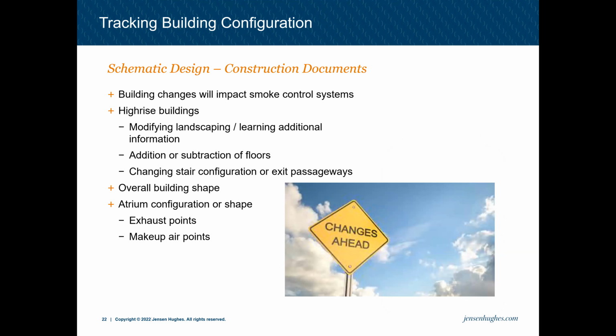So throughout design of a project, we always need to be tracking the building configuration. Building changes can impact smoke control systems. So for instance, for high-rise buildings, if you're modifying the landscape or learning additional information, that we've seen before can change high-rise classification. And we've seen some projects where they start to do sloping and grading, and all of a sudden a building that was not a high-rise or was not requiring smoke control, after some site work is done or roads get planned out, becomes a high-rise needing stair pressurization or elevator pressurization.